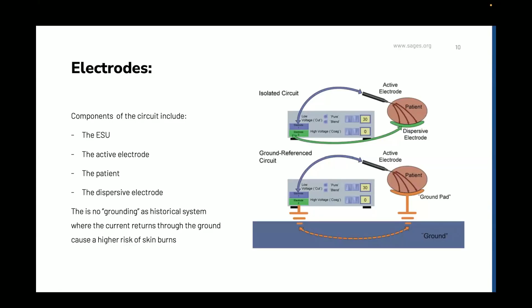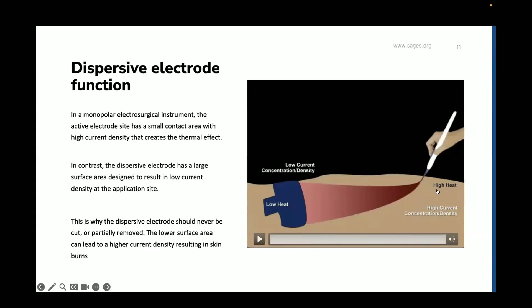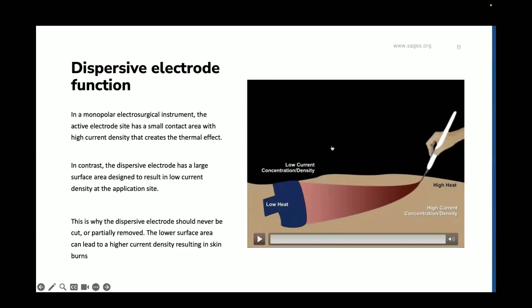The way the dispersive electrode works is that it'll take the current that is delivered through the active electrode, and it takes it back through a higher surface area, so that it leads to a lower current density. So the tip of your active electrode has a very high current density because of its low surface area. So this leads to the tissue effect of heating up the cells to high temperatures, whereas that same current comes back through the dispersive electrode and back to the ESU through a higher surface area with much lower current density and heat.